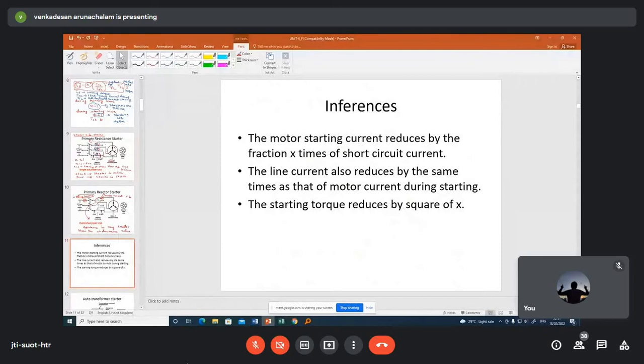primary resistance starter and primary reactor starter. See here, we are reducing the starting current, that is an advantage to us, but the starting torque is reducing by X squared times. I told you that if the starting torque reduces at one point of time, the motor refuses to start itself. So that is the demerit in this starter. The starting torque reduces by the square of X.